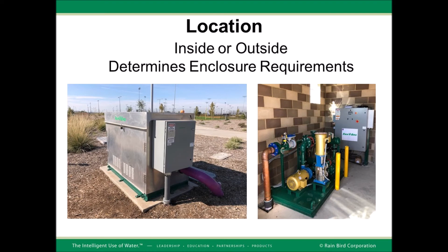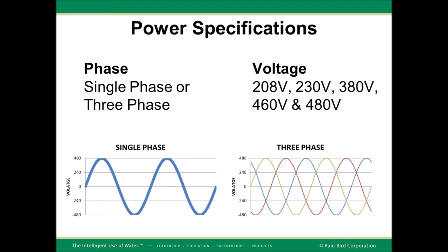Another very important factor is the power specification at the site. Sometimes we may not know that when we are specifying the irrigation plans, but we could provide single phase or three phase power supply at different voltages from 208 to 230 to 480 volts. It's very important before the pump is installed to confirm this power specification, and you can have it as a note in your plans for the contractor to confirm this.